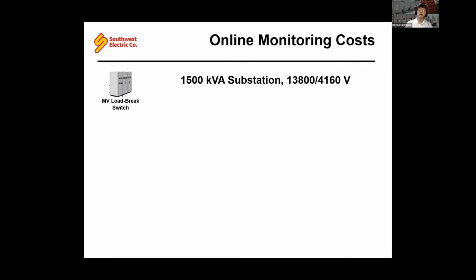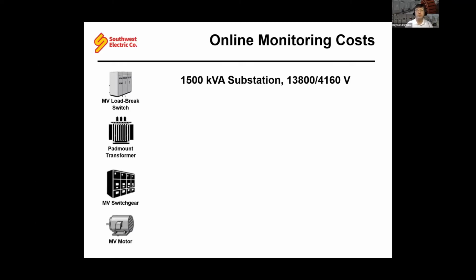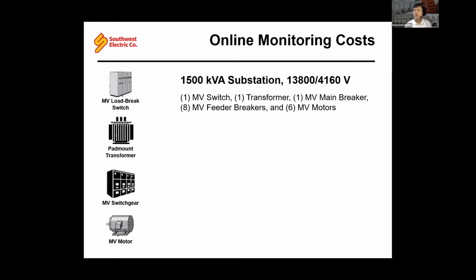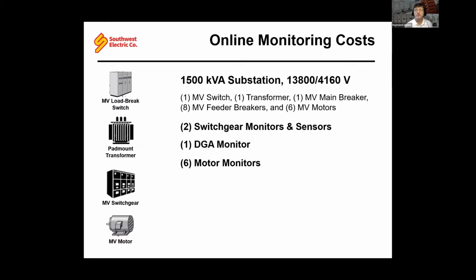And so if you have a typical substation with a primary load break switch to a transformer to some switchgear that will feed some motors, and we have this as an example. This is our typical, I don't know if typical, but it's average substation. In order to provide online monitoring for the substation, you're going to need the switchgear monitors, sensors. You're going to need your dissolved gas analysis monitor for your transformer. You're certainly going to want to monitor on each of your motors.